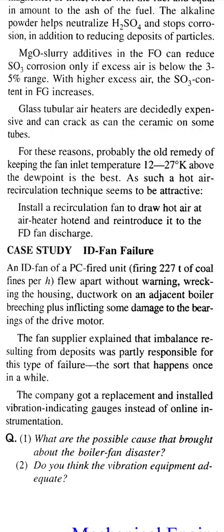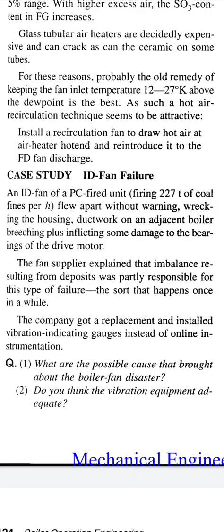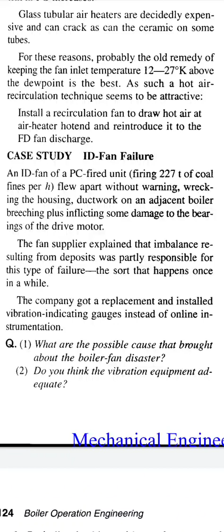An ID fan of a PC fired unit firing 227 tons of coal fines per hour flew apart without warning, wrecking the housing and ductwork on an adjacent boiler, plus inflicting some damage to the bearings of the drive motor. The fan supplier explained that imbalance resulting from deposits was partially responsible for this type of failure. This sort of thing happens once in a while. The company got a replacement and installed vibration indicator gauges instead of online instrumentation.